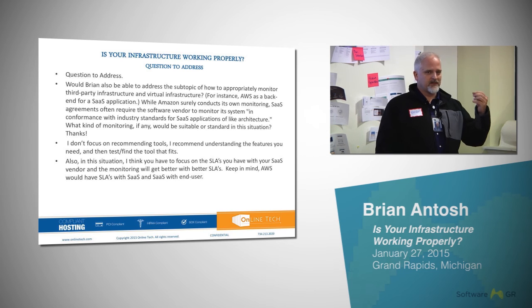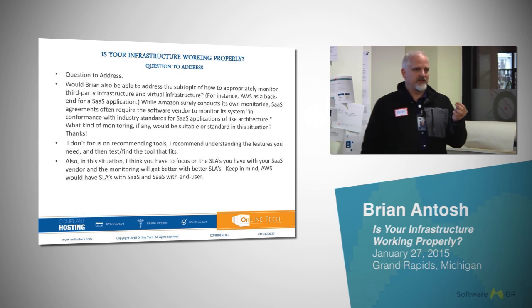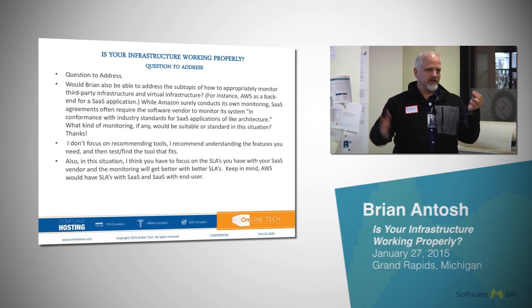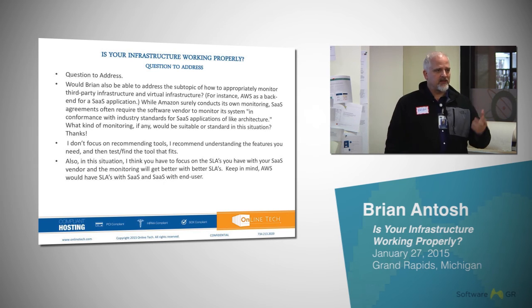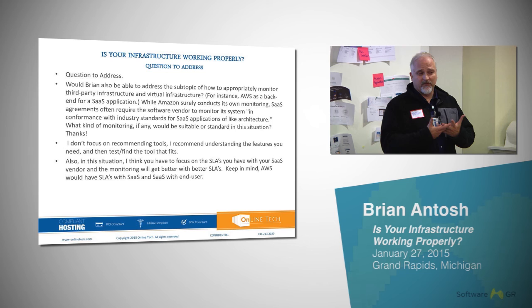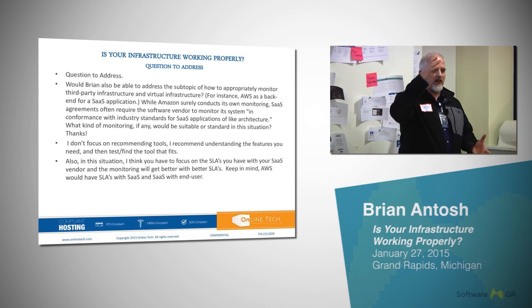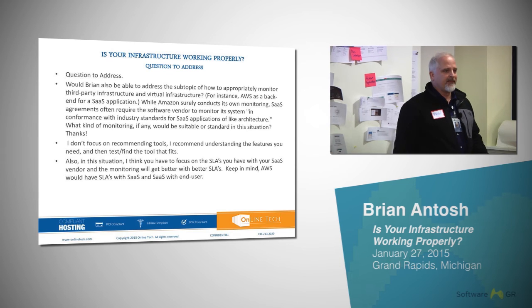Like a leak detect, there's a lot of nuisance alerts. Your program or the person watching this might go like this: if it clears within 5 minutes, then don't send the alert out. If you have the alert, someone's got to go check it out. On AC, a lot of alerts don't affect the performance, but they need to be checked out. And then there are critical alerts, like the compressor's in high head pressure. That means that compressor's not cooling. You've got to do something about it now. So there's this whole triage knowledge of alerts, because it's a flood of them.